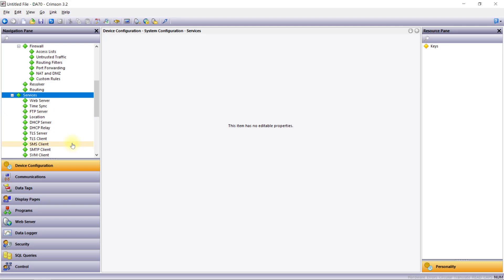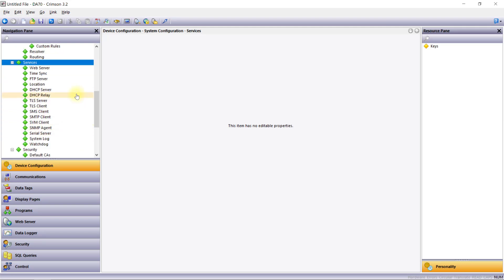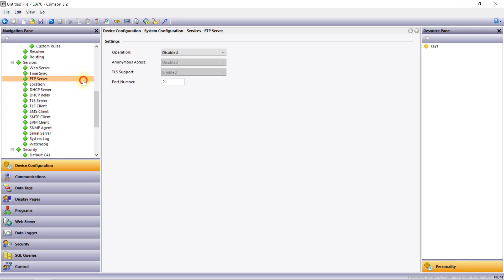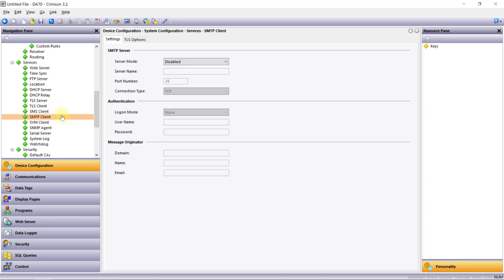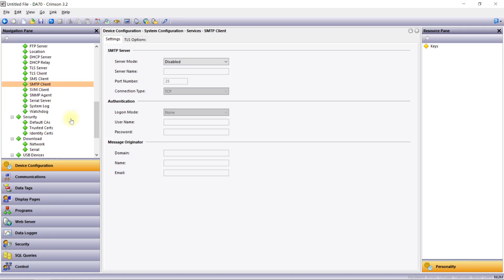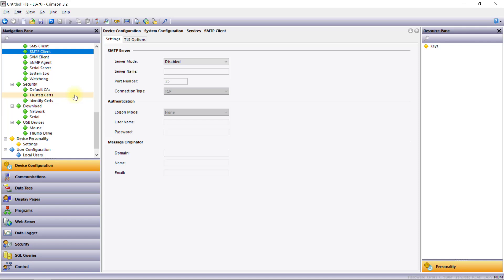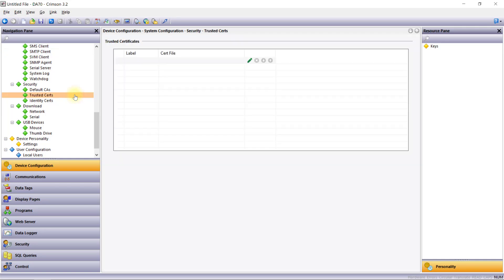The Services section is used to configure several network services hosted by the device. Some examples of network services' use cases include the FTP server for data log retrieval and the SMTP client for email alerts. Users can also find options for time synchronization, DHCP server settings, and more in this section. The Security section is used to configure various types of certificates. For example, if you'd like to use TLS for a secure MQTT connection, you could start by adding the TLS certificate into the Trusted Certs section here.